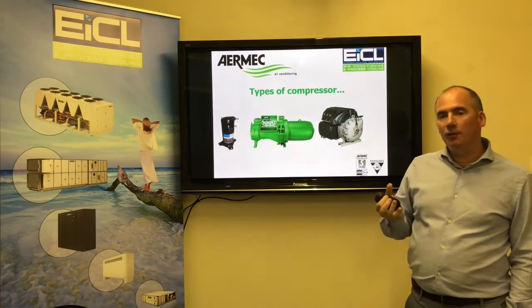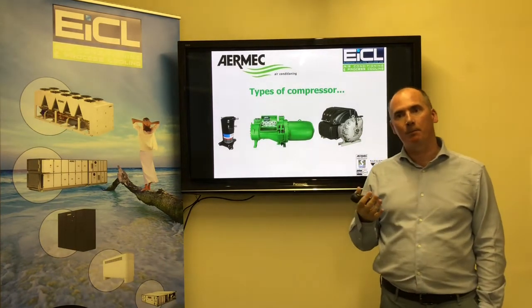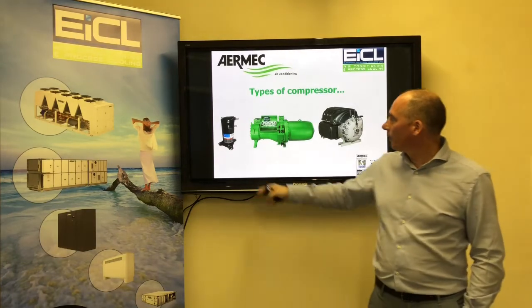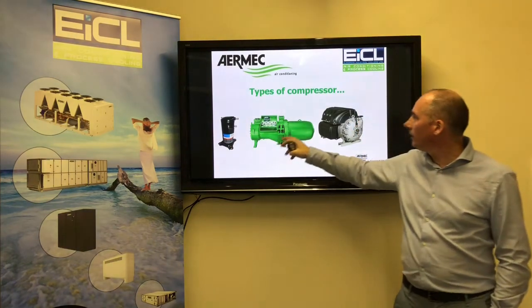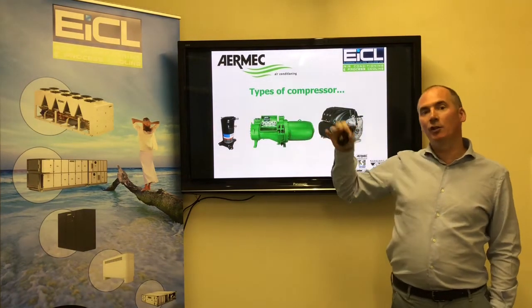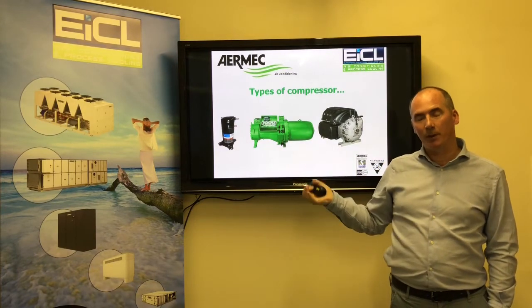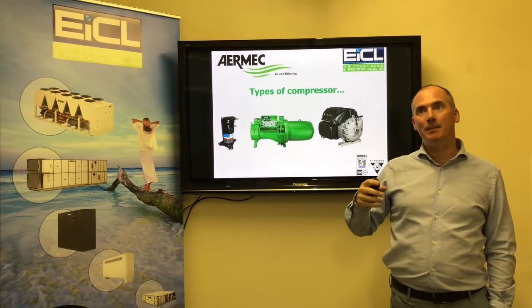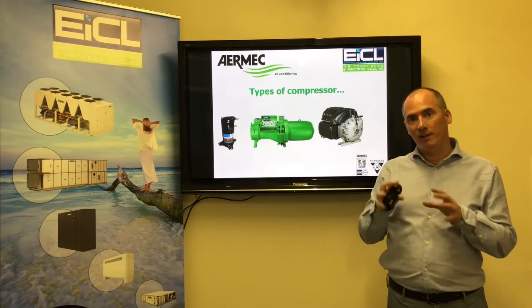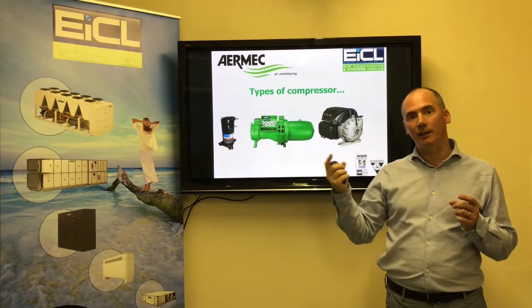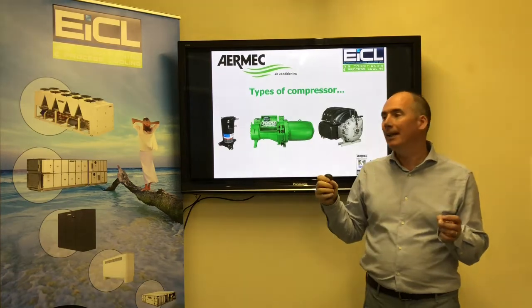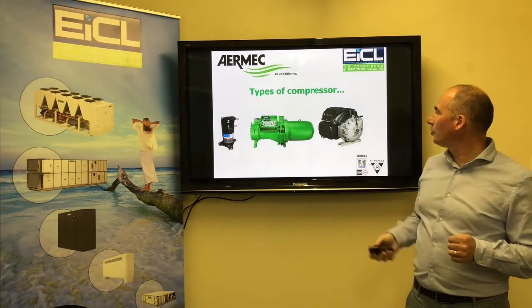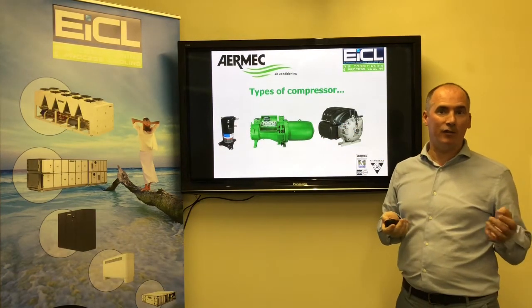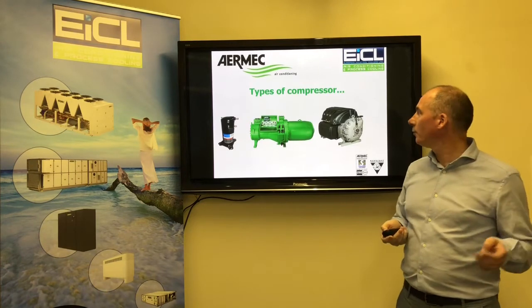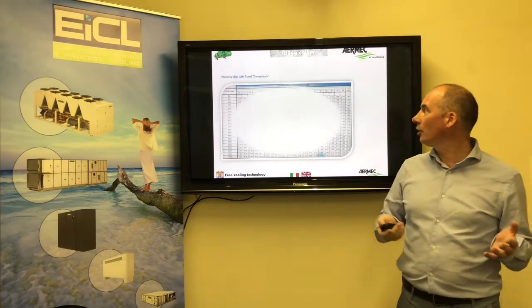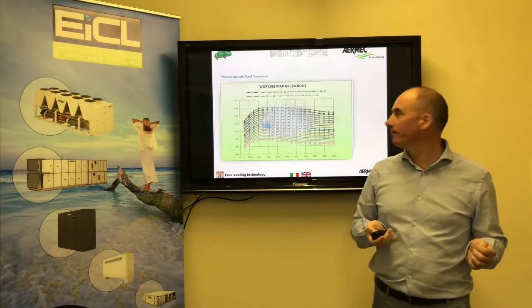So different types of compressors would have different performance characteristics. So for example, this would be a scroll type, this would be a screw, and you can have a non-inverter and an inverter type screw, by the way. The non-inverter simply means the rotor runs at the same speed and they would typically recirculate the refrigerant with a slide valve or something like that. And then of course you would have a Turbocor as an option. There used to be also piston reciprocating compressors, but they're pretty much obsolete now in chiller manufacturing.